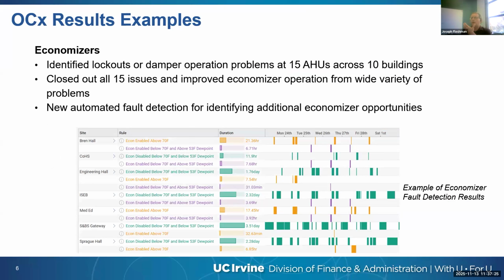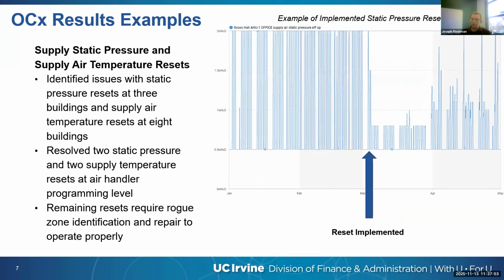Economizers. So we identified lockouts or damper problems at 15 air handlers. This is a pretty common problem where we are. We're close to the coast, and so outside air dampers tend to freeze up, especially older galvanized steel ones. The moist, kind of sea water type air will corrode those. We closed out all 15 of those. We improved the economizer operations. We've added some additional fault detection for additional economizer opportunities, which I'll talk briefly about later. Supply static pressure and supply temperature resets.